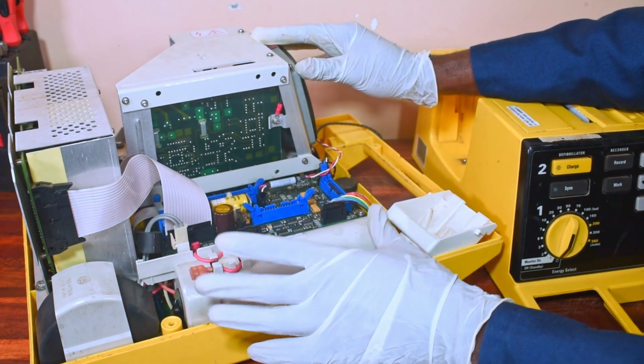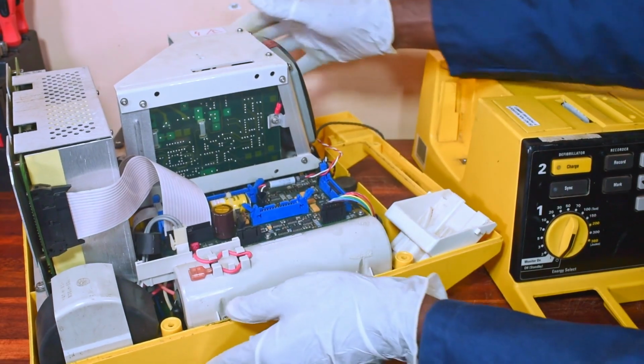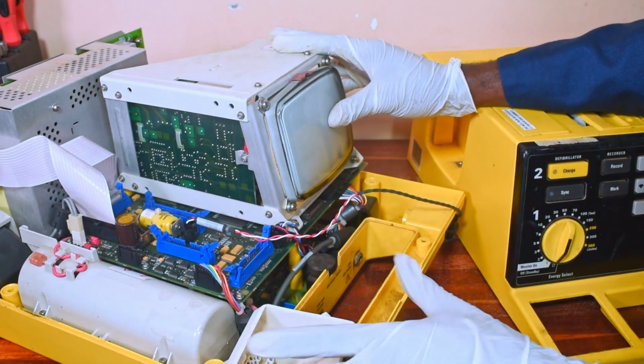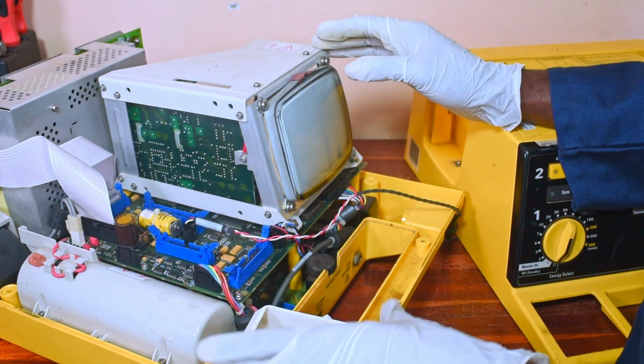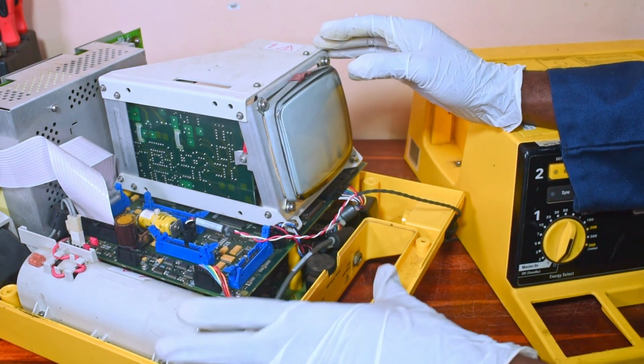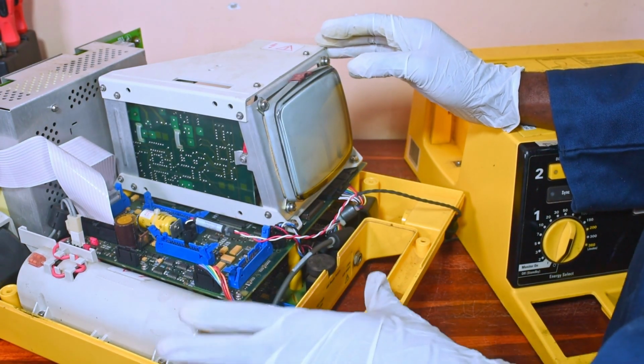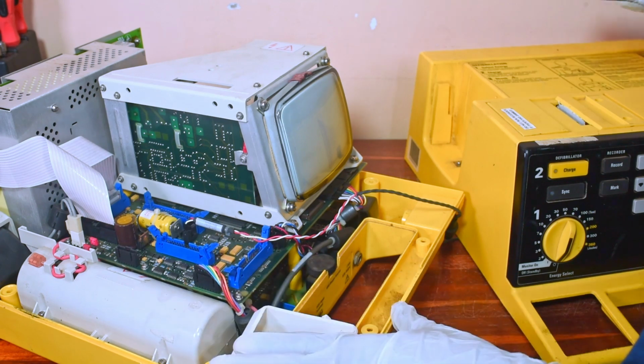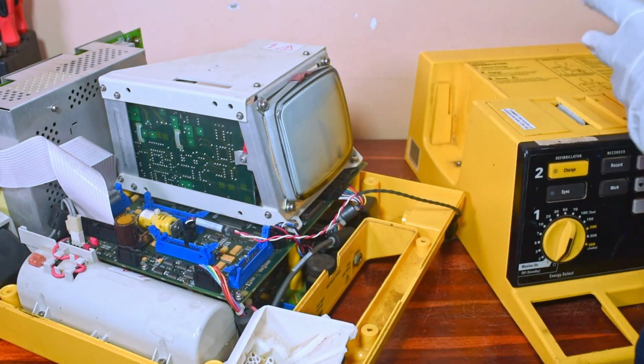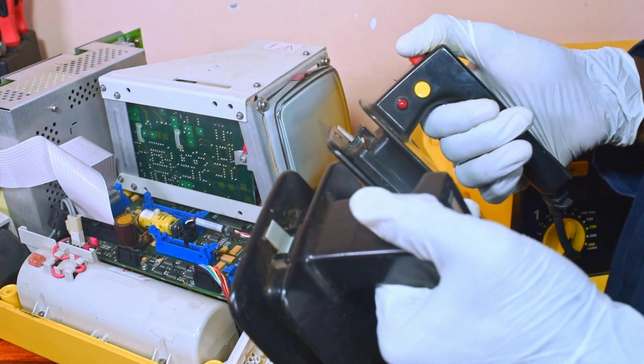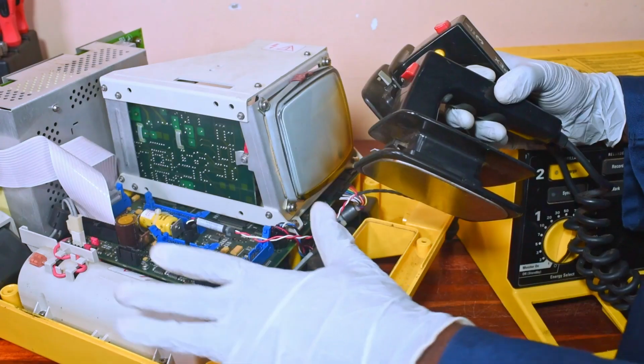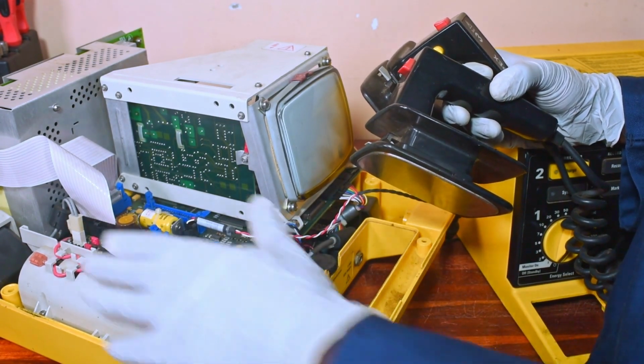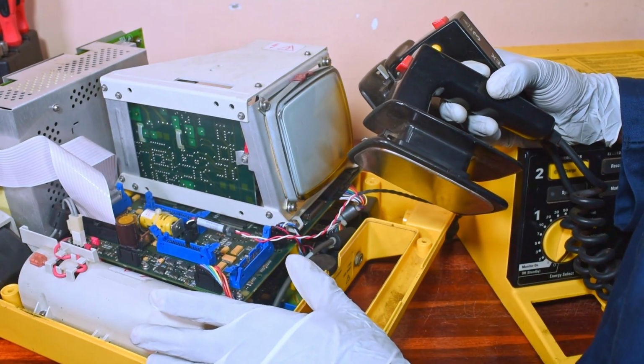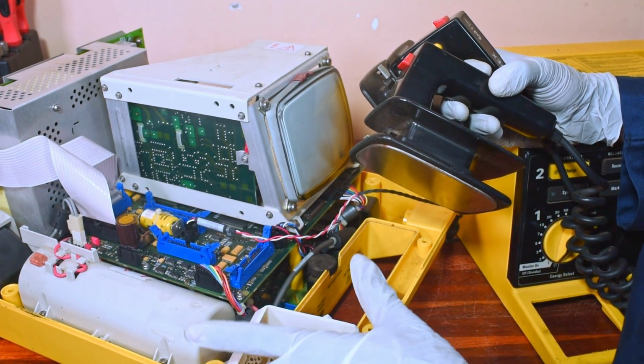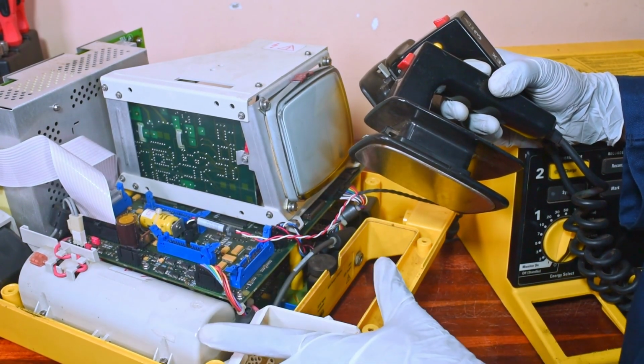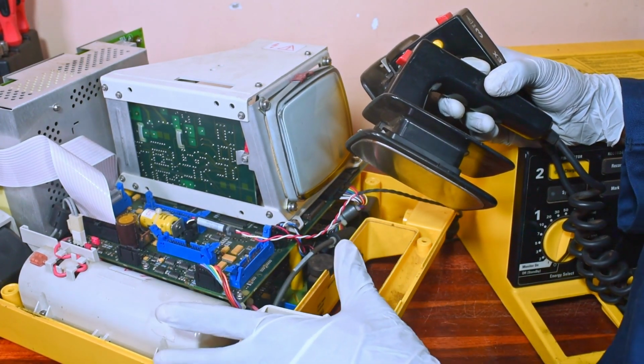The high voltage capacitor is fully charged if the charge done indicator illuminates. The monitor displays the available energy in joules. If the defibrillation energy is decreased, the safety relay closes to trigger an automatic high voltage capacitor discharge. During a shock, defibrillation energy is delivered to the paddles once the shock buttons are pressed. The high voltage capacitor is discharged through the patient inductor into the patient load. The patient relay isolates the high voltage board from the capacitor. In defibrillation mode, this energy is instantly delivered to the patient.